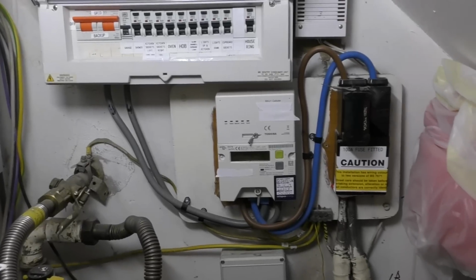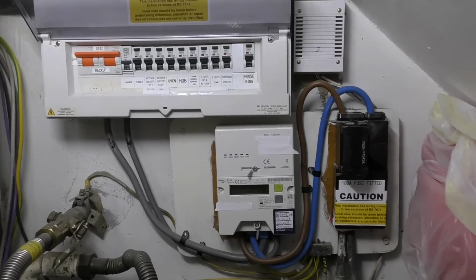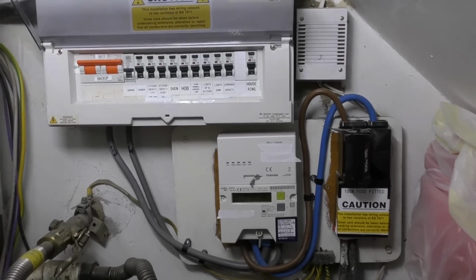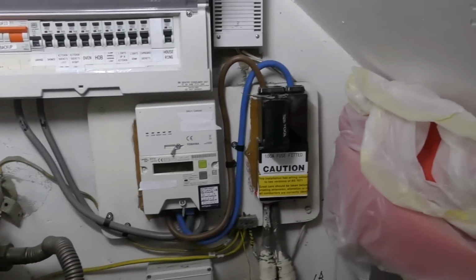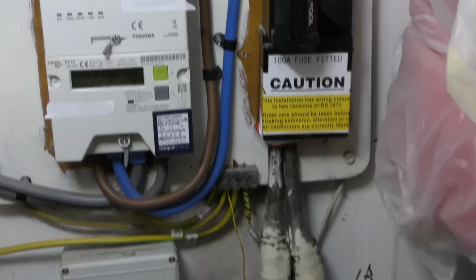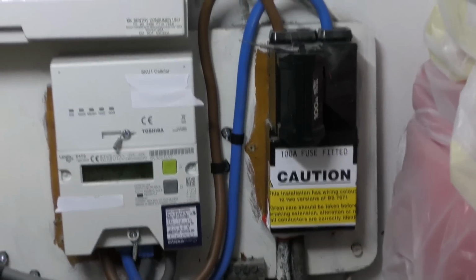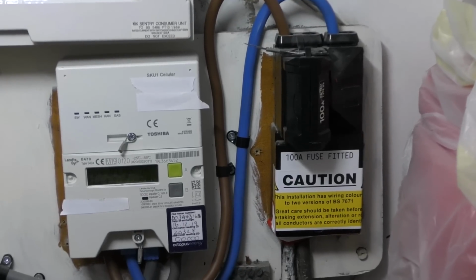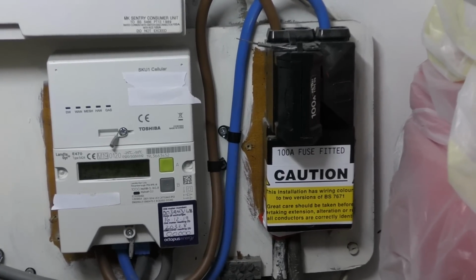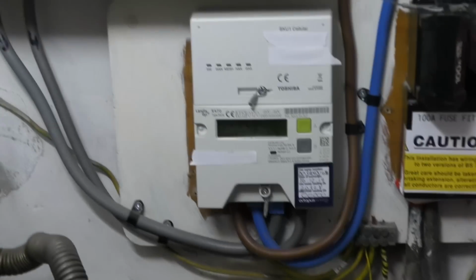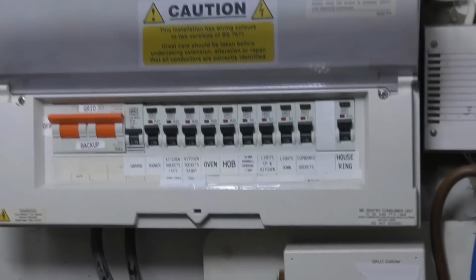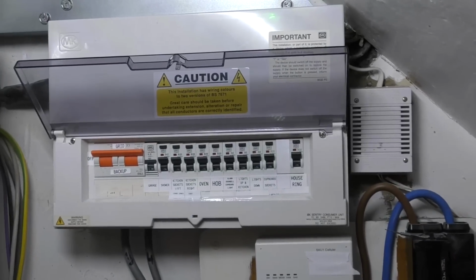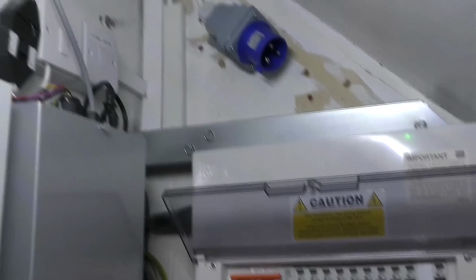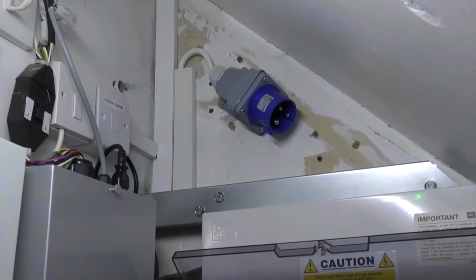This is my house setup. Now, one reason I didn't go for that changeover switch in the external box, I just didn't have space. You can see we've got the incoming cutout. This is basically where the power comes into the house. This is very typical of what you see in UK houses. This has got a 100 amp fuse fitted, and then that goes into the meter, and then that goes into the distribution board, often called a consumer unit in the UK. As you can see, I don't really have a great deal of space, so I've put the 32 amp inlet up there, and there's not really space for anything else.